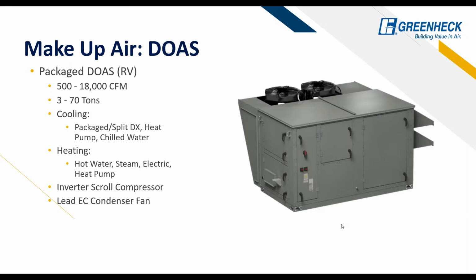Okay, moving into the DOAS as well. You can go with the DOAS unit as well. You don't have to just go with these makeup air ones. With the DOAS unit, I would not supply these right at the hood because this is an expensive unit. It costs money to cool this air down. So you don't want to just put it right in the hood and then out to space. This would be more of an application where you're supplying it into the entire kitchen area, or even if you have a small restaurant, think like a takeout, like a Shake Shack type thing, where you can just have a DOAS in the dining room and it will serve dining room tempering and makeup air as it flows towards the hood. So that is an option as well.